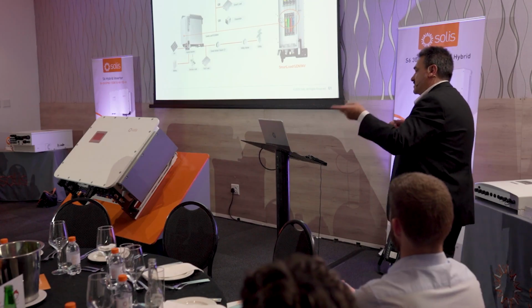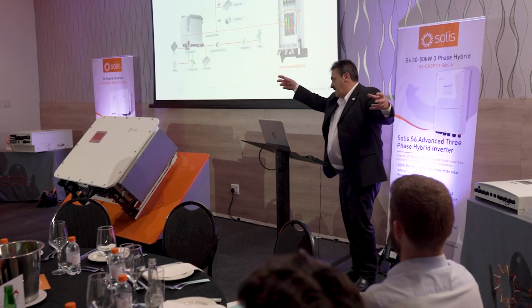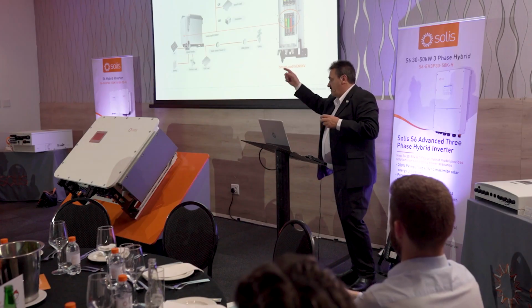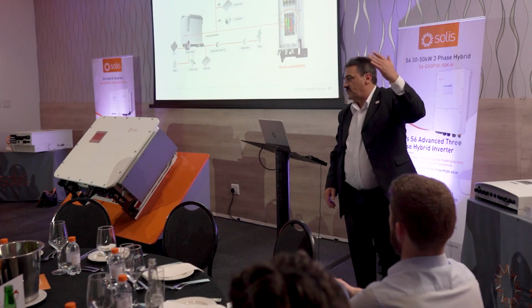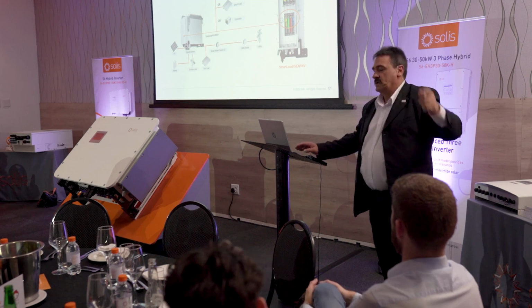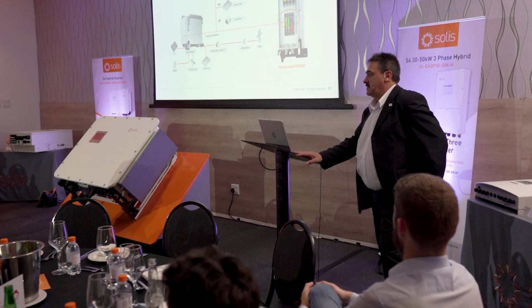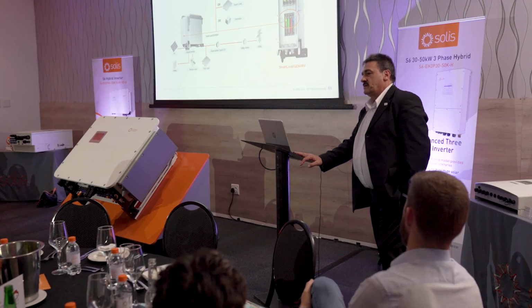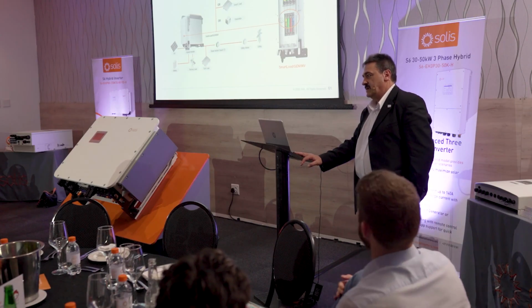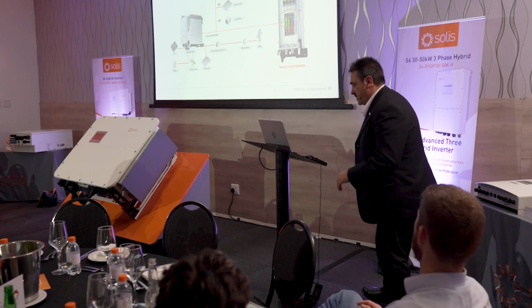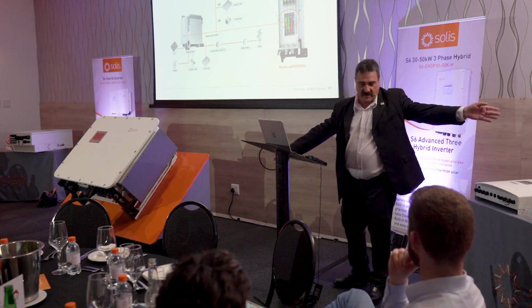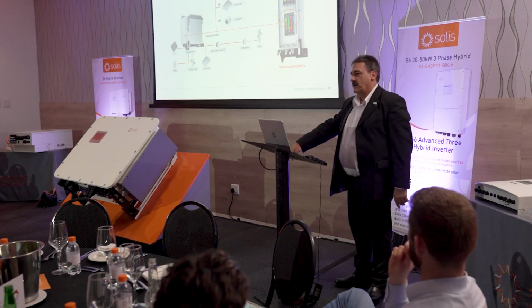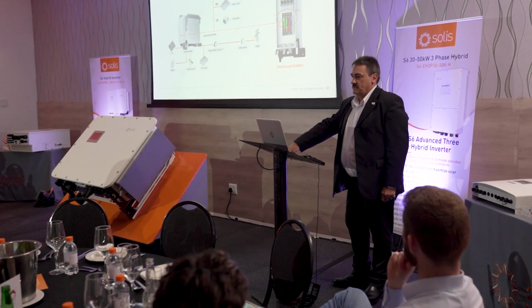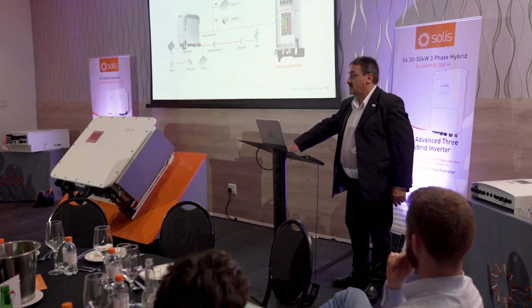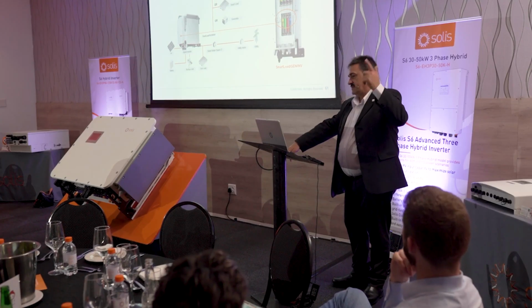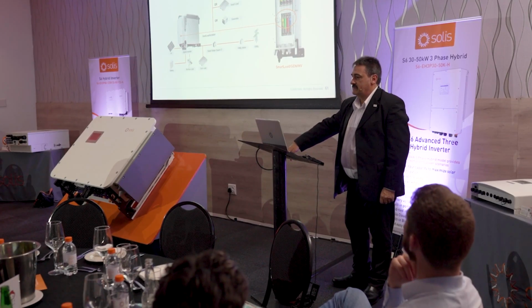Home run is long, size of the cable is too thin, and for the inverter to get that amount of current over there, the only way to do it is to increase the voltage. Then the guy says, oops, inverter keeps going into over voltage. It's not that. It's the cable is too small. We've seen that time and time again. You can actually see it very clearly. We've got a 50 kilowatt inverter, and once it gets to like 30 kilowatt, the guy starts getting over voltage alarms. Below that it works fine. But as the power increases, all of a sudden you start getting alarms. It's a dead giveaway.